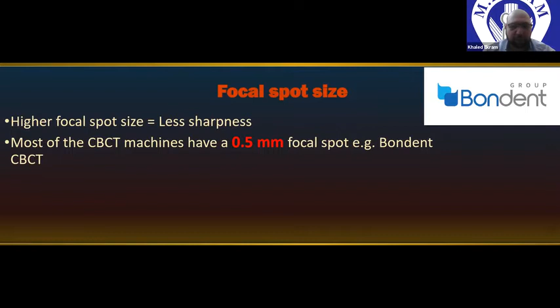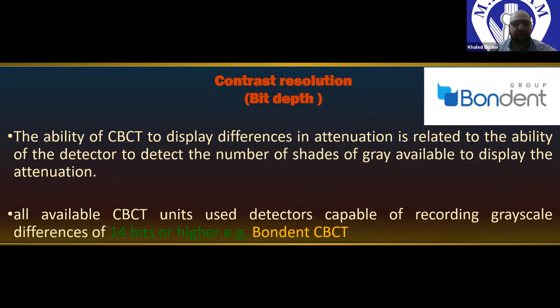Contrast resolution, or what we call the bit depth. The contrast resolution is a function that displays the different bone densities or tissues of different CBCT or CT numbers. So the higher the bit depth, the more ability for the machine to display different structures and differentiate between enamel, for example, dentine, and cementum and bone, between cortical and spongy bone. So the range that we are talking about is that we should have 14 bit depths or more, such as the Bondent CBCT, which has 14 bits.